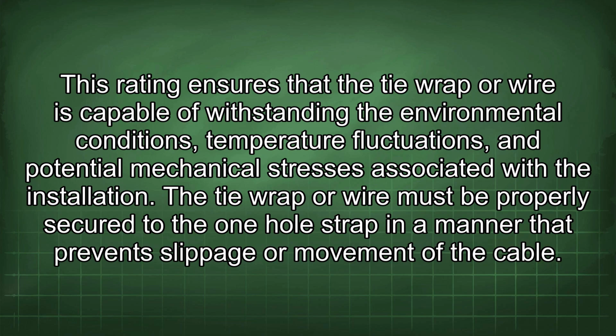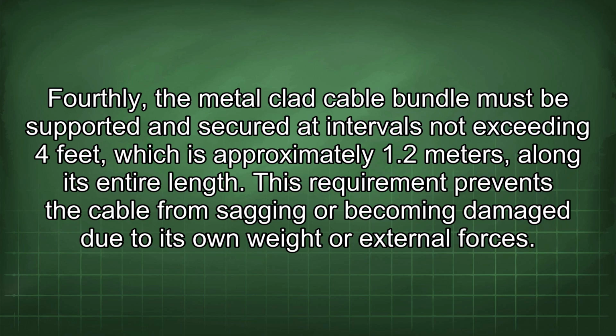The tie wrap or wire must be properly secured to the one-hole strap in a manner that prevents slippage or movement of the cable. Fourthly, the metal-clad cable bundle must be supported and secured at intervals not exceeding 4 feet, which is approximately 1.2 meters, along its entire length. This requirement prevents the cable from sagging or becoming damaged due to its own weight or external forces.